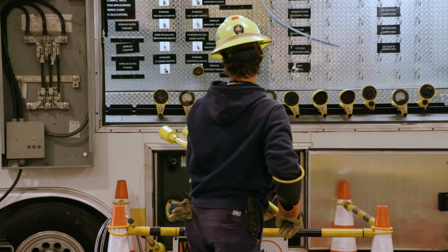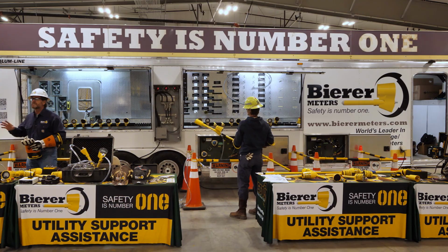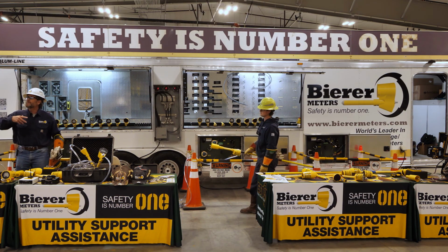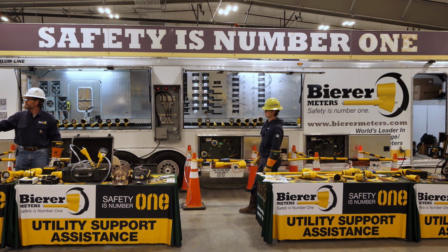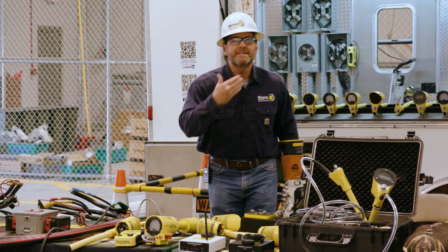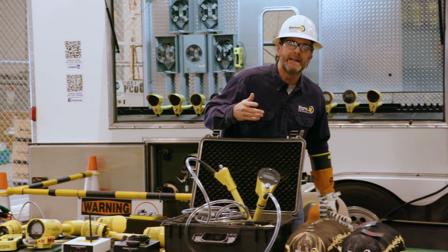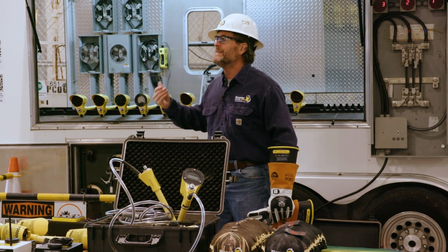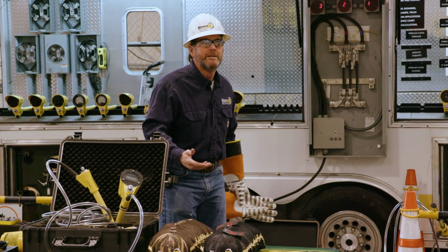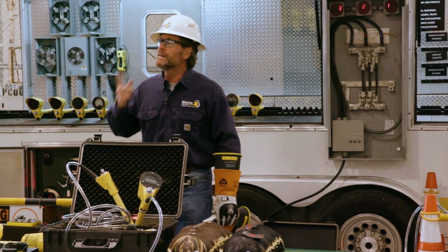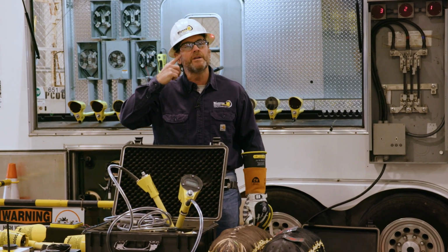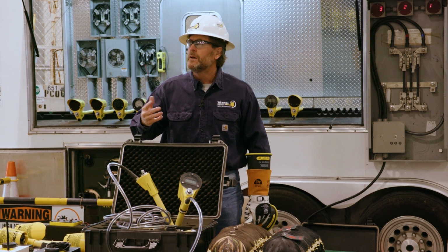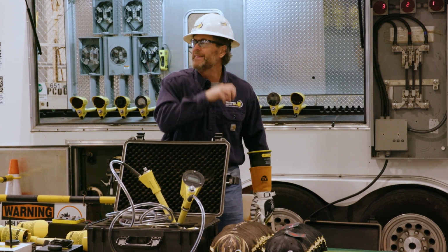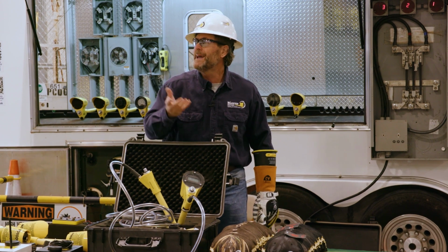0. Okay, 0. The reason why you want to always take the meter head off last is you want the meter to speak to you. When the meter speaks to you and you see zeros on that tool, then the meter is telling you that the tool is de-energized. Okay? So that's how we're going to do this all the time. You don't have to. You could go to the meter probe first and then the secondary probe second. You can, in high potting and phasing, but because you understand how the tools function and work, you always do the secondary probe first and then let the meter probe tell you the information.